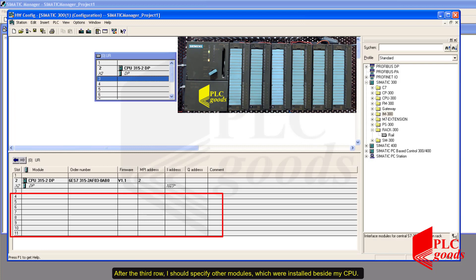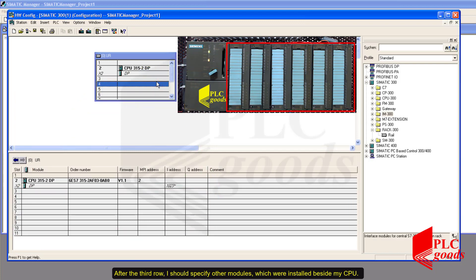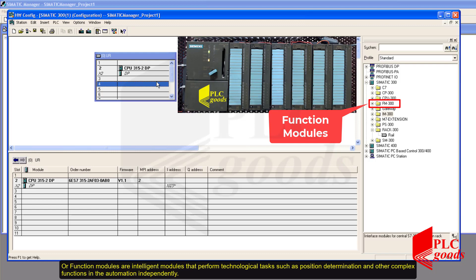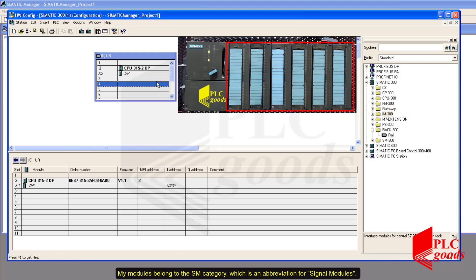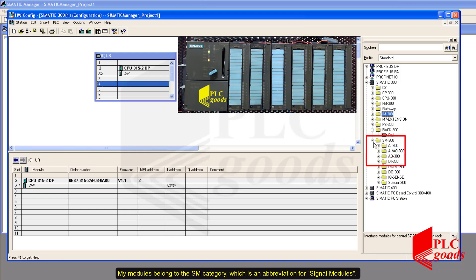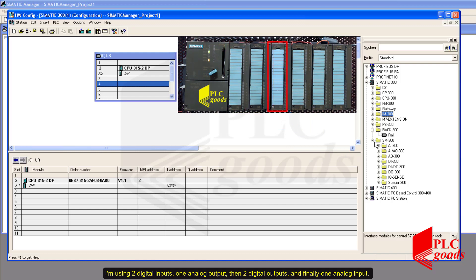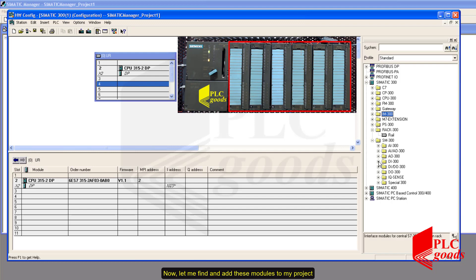After the third row I should specify the other modules installed beside my CPU. There are lots of modules — for example, CP modules are used to transfer data in the case of not having the required port on the CPU. Function modules are intelligent modules that perform technological tasks such as position determination and other complex functions independently. My modules belong to the SM category, which stands for signal modules. Signal modules are the interface of the CPU to industrial processes. I'm using two digital inputs, one analog output, two digital outputs, and finally one analog input. Now let me find and add these modules to my project.